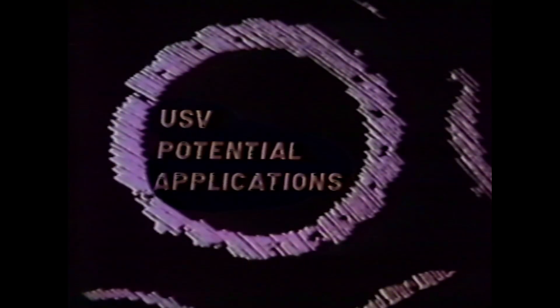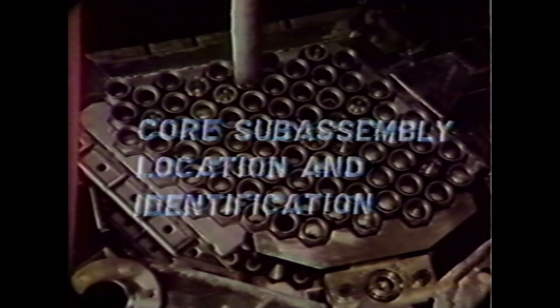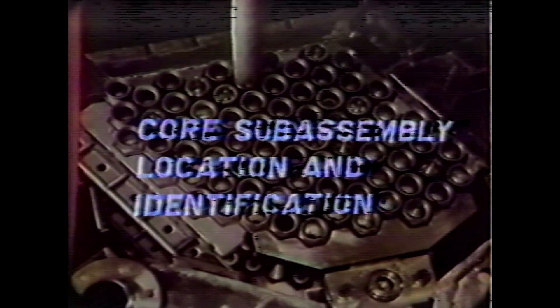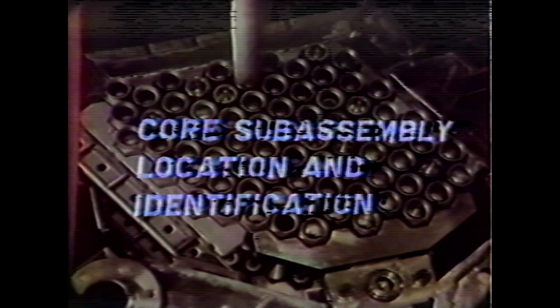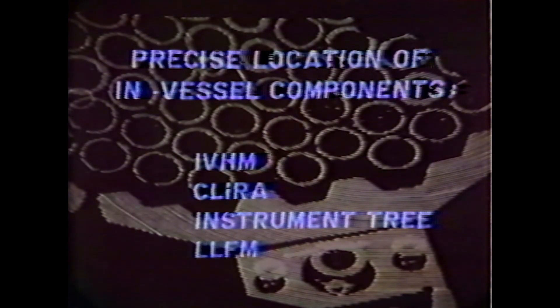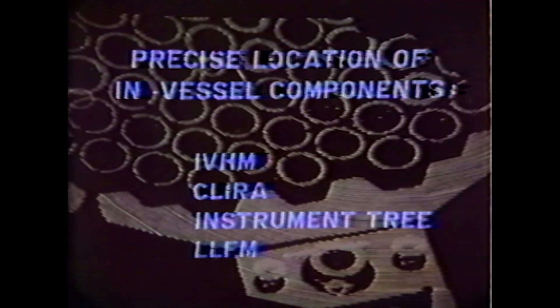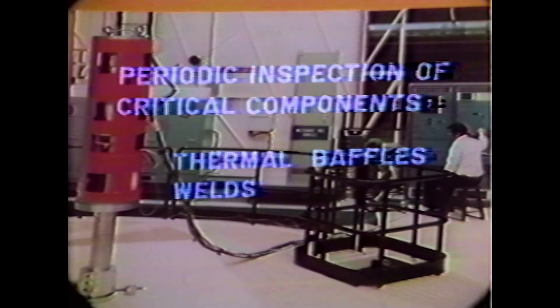Application of this system will permit core sub-assembly location and identification, precise location of in-vessel components, periodic inspection of critical components such as thermal baffles and welds, and search and retrieval guidance information for misplaced or foreign objects.